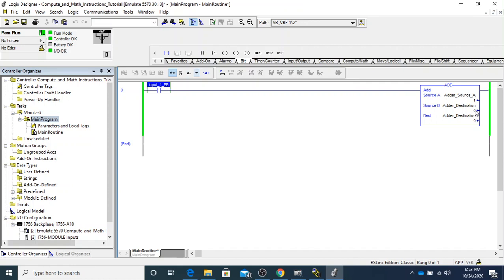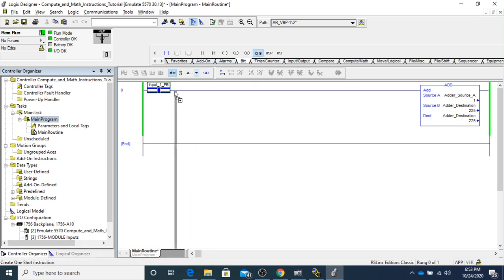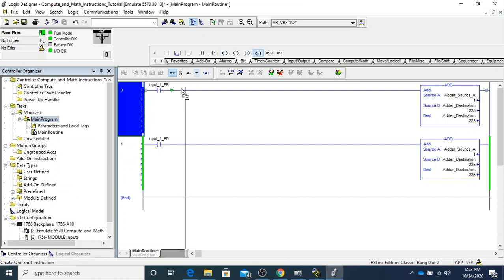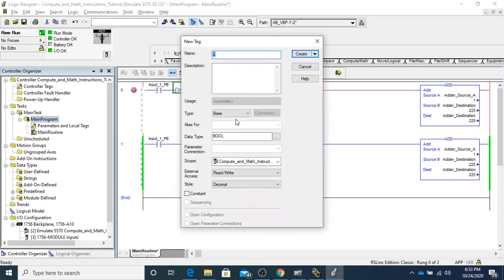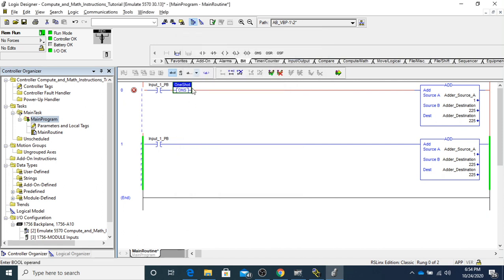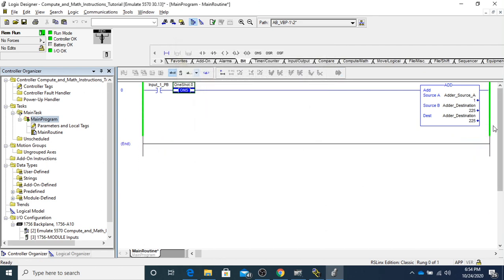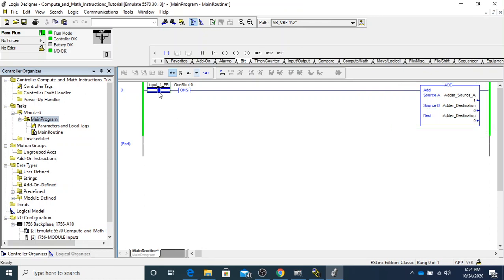Every time we toggle the input it counts up — one plus one is two, and so on. But as you can see, when it's just on it keeps going continuously. This is where we want a one-shot. I need to go back into edit mode — we're going to add a one-shot, make it a DINT, add a dot zero bit, and set the destination back to zero for the one-shot storage.